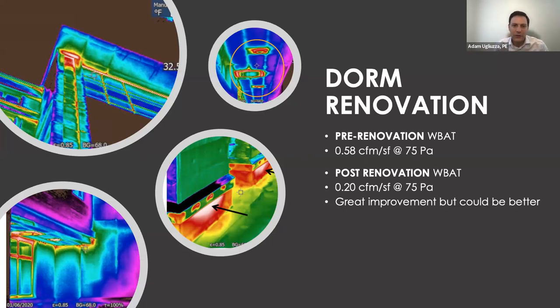There's a lot of holes that you can have. Not to promote having holes, but there is some leeway there, and you can still pass the test. But as I mentioned, we always recommend that if we do find something with an infrared scan or smoke, you go back, evaluate the risk there, and try to repair everything, even though you've passed the quantitative test.